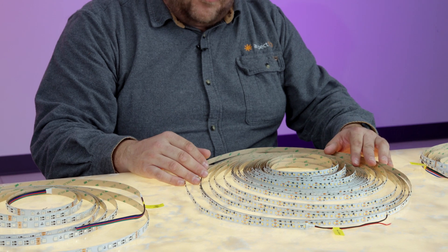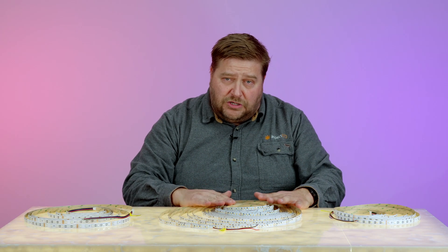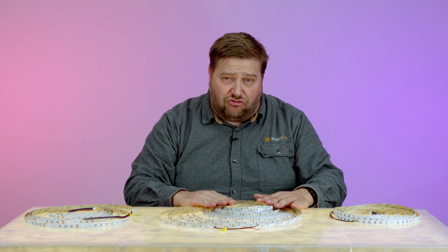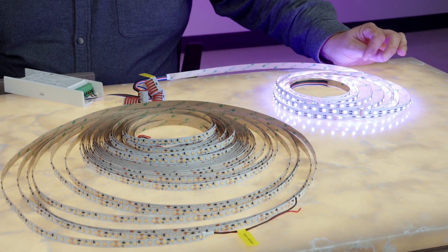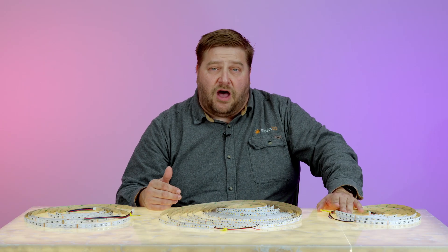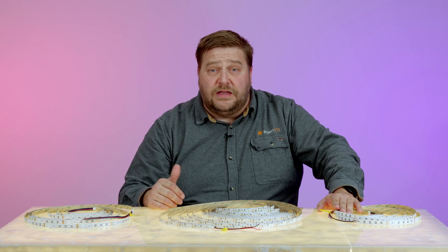The hookup for this is exactly the same as it would be if you were using a constant voltage or traditional strip light. For the single color, we do want to use PWM dimming, or an electronic dimmer or electronic power supply and dimmer. For the RGB and the RGBW, these can be connected to a controller such as our Z Series controller or the Casambi controller. They can also be controlled via DMX.